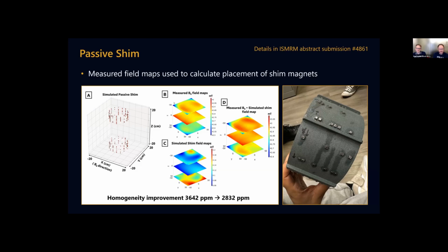And then in B, you could see the measured magnetic field before shimming. Then you can see the simulated shim field maps. And then D was the field after placement of the shim magnets, so it's basically the shim magnets and the main magnets together. And we managed to improve the homogeneity by maybe 1,000 or 800 ppm or so. And our more recent versions are actually better than this as well.